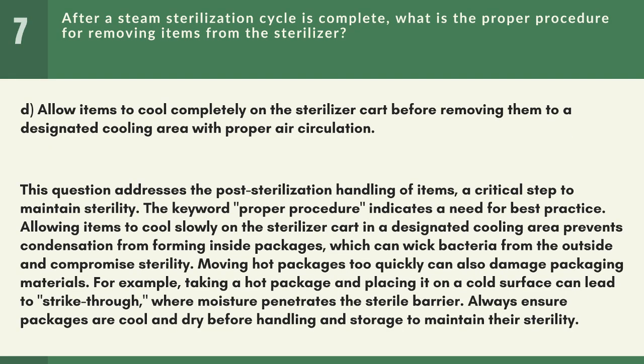Answer: D. Allow items to cool completely on the sterilizer cart before removing them to a designated cooling area with proper air circulation. This question addresses the post-sterilization handling of items, a critical step to maintain sterility. The keyword "proper procedure" indicates a need for best practice. Allowing items to cool slowly on the sterilizer cart in a designated cooling area prevents condensation from forming inside packages, which can wick bacteria from the outside and compromise sterility. Moving hot packages too quickly can also damage packaging materials. For example, taking a hot package and placing it on a cold surface can lead to strike-through, where moisture penetrates the sterile barrier. Always ensure packages are cool and dry before handling and storage to maintain their sterility.